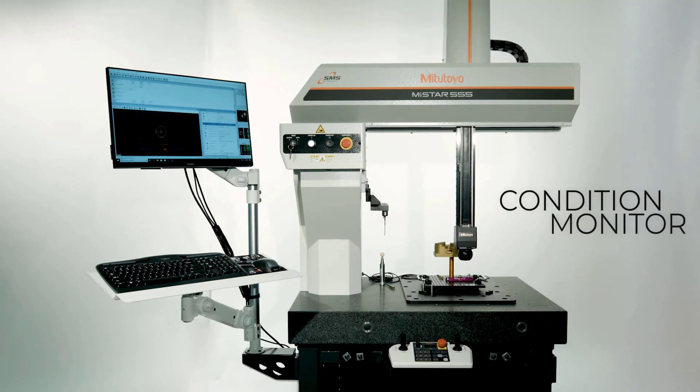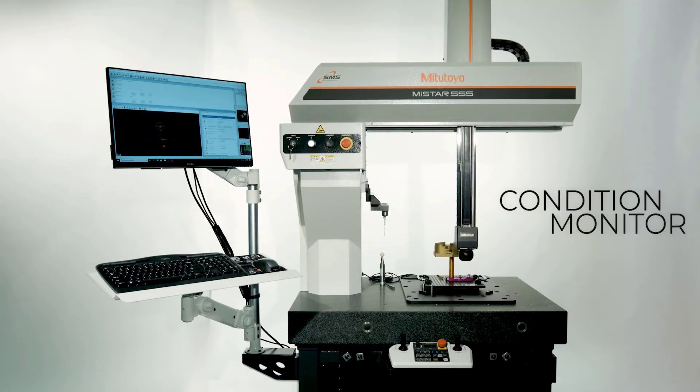Condition Monitor monitors key CMM control parameters for long-term tracking of the CMM mechanical, electrical, and probe system components for preventative maintenance in visual reports and alerts.